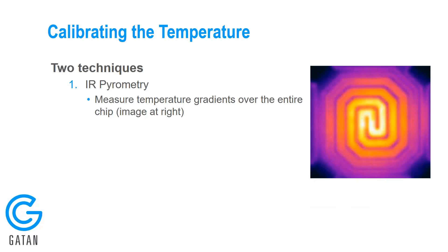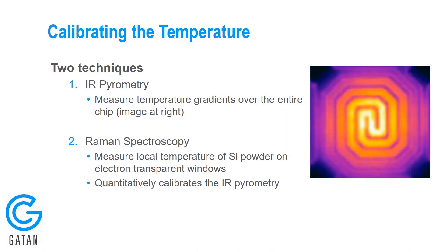How does DENS Solutions calibrate the temperature of their chips, and why should a researcher trust this calibration? DENS Solutions uses two techniques. The first is infrared pyrometry, which allows them to measure temperature gradients over the entire chip. But infrared pyrometry is difficult to calibrate precisely. They also use Raman spectroscopy, which allows them to measure the local temperature of a sample on the electron transparent windows. This allows them to quantitatively calibrate the infrared pyrometry and to calibrate the temperature of the chip based on the temperature of a sample — not based on the temperature of the heating element or some other location.